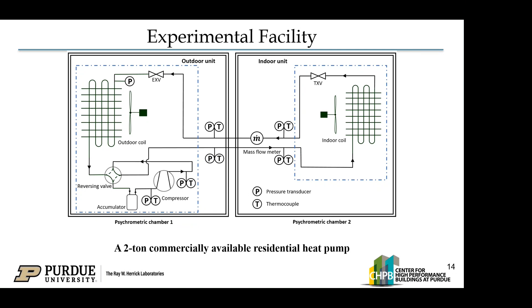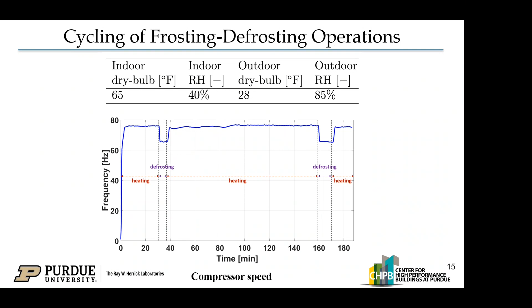It spans 3 hours, and from the compressor speed, we can see that after it starts up, at 30 minutes, it switched to the first defrost cycle. For this specific system, it never shut down. During defrost, it just ran at a lower speed. And then it goes through a 2-hour heating period, then switches to the second defrost cycle. So if our model can capture this complicated dynamics with multiple cycles of heating and defrosting, then it demonstrates the model's capability for the objective.